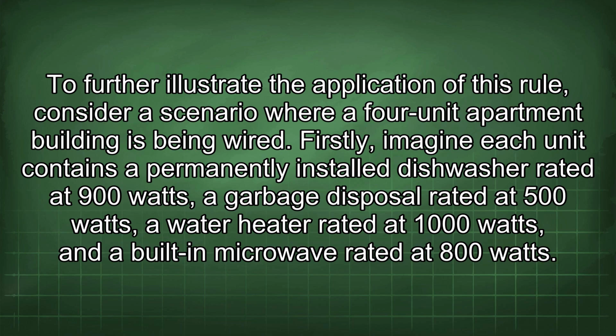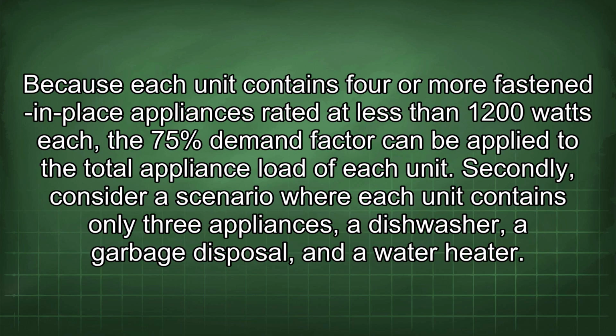Firstly, imagine each unit contains a permanently installed dishwasher rated at 900 watts, a garbage disposal rated at 500 watts, a water heater rated at 1000 watts, and a built-in microwave rated at 800 watts. Because each unit contains 4 or more fastened-in-place appliances rated at less than 1200 watts each, the 75% demand factor can be applied to the total appliance load of each unit.